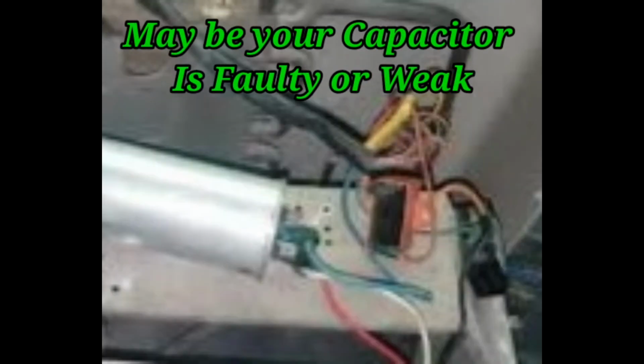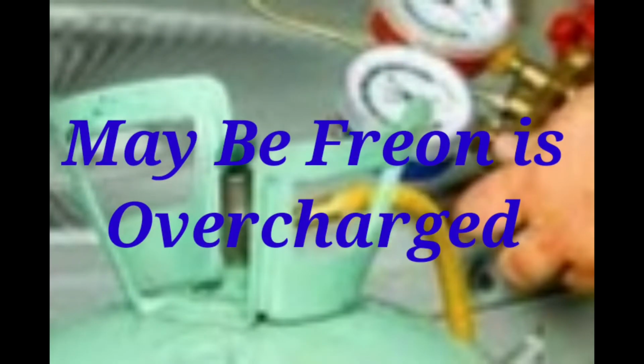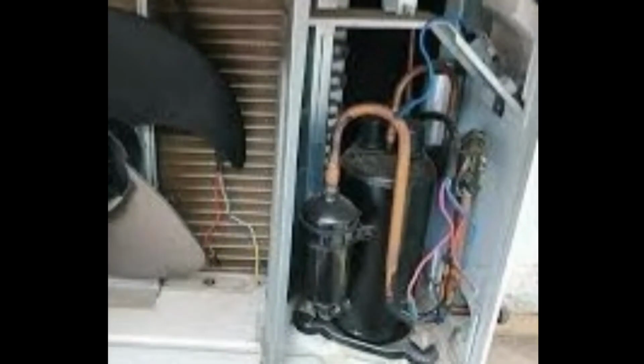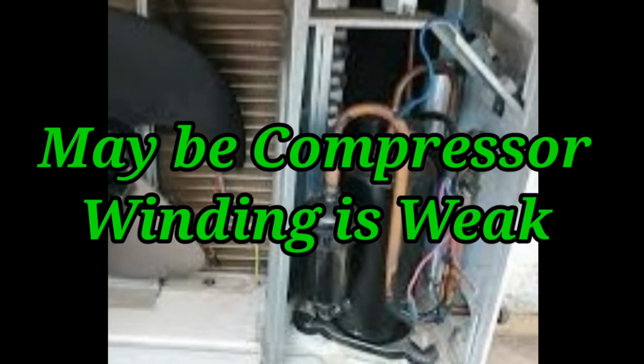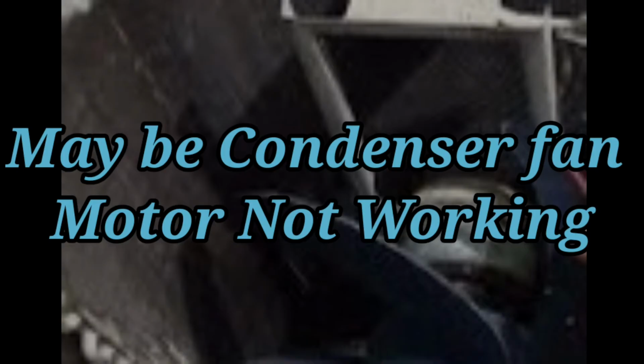First reason is that maybe your capacitor is faulty or weak, so you must check that your capacitor is working okay or not. Another reason maybe you charged too much freon in the unit, that's why the compressor heats up. Or another reason maybe the compressor winding is weak, you can check with a multimeter whether the winding is okay or not. And maybe your condenser fan motor is not working. This is also one of the reasons why this AC is overheating and H3 is coming.